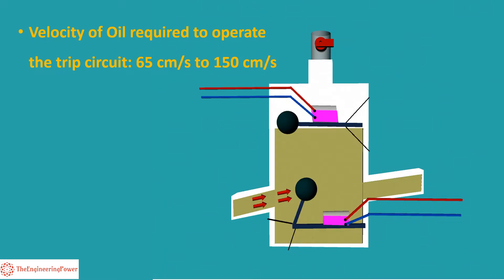In most Buchholz relays, provision is made for adjusting the relay to operate at 65 cm per second, 100 cm per second, and 150 cm per second. Most commonly, these relays are set at 100 cm per second.